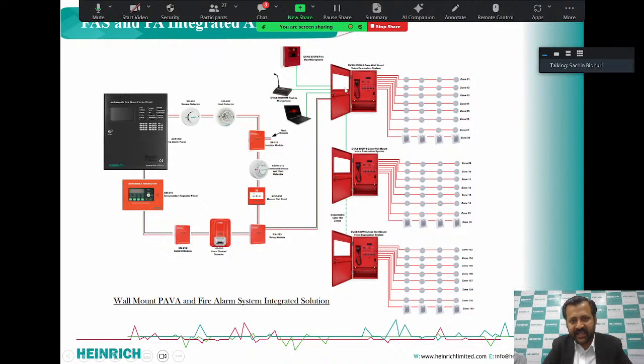So this is basically an architecture where we have shown our two solutions integrated into one. We can make a manual announcement as well, and we can have an automatic announcement through our PA system. In our PA system, if a signal is given from the fire alarm system, it has the highest priority. Other systems get priority below it. So if there is a fire, the highest priority is given to the fire signal or the message that has been pre-recorded in our PA controller. So this is basically an integration.